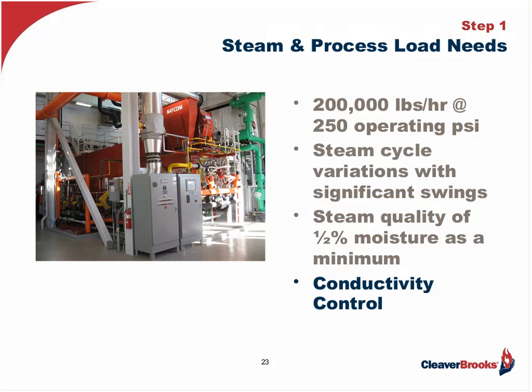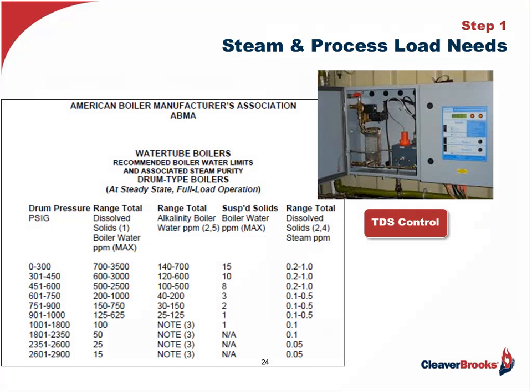Going back to the cyclic load, the next thing to consider is the conductivity level on the boiler. We need to keep it within specific ranges to avoid foaming or priming in the upper drum, which causes carryover and adversely affects the process while adding to the possibility of water hammer. We're looking at holding tolerances for hardness, alkalinity, and TDS — total dissolved solids — in the feedwater while maintaining a specific conductance level measured in micromhos. Most people follow the ABMA — American Boiler Manufacturers Association — water quality table for saturated steam applications. ASME has also published Table 1, which is good for superheated steam applications, particularly for power where steam spins turbines. As a consulting engineer, make sure you understand the purpose of the steam and determine which table to use.